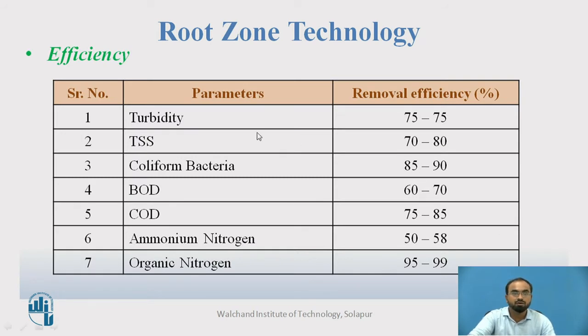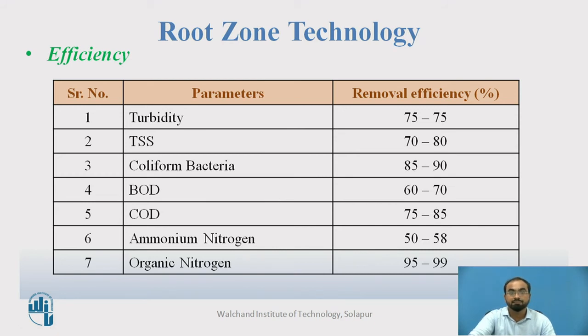The effluent water shows a turbidity removal efficiency of around 75 percent. TSS removal is around 70 to 80 percent. Coliform bacteria removal efficiency is around 85 to 90 percent. BOD removal efficiency is relatively lower, but if a multi-digestive system is used, it can increase. For pure root zone technology, BOD removal is around 60 to 70 percent.